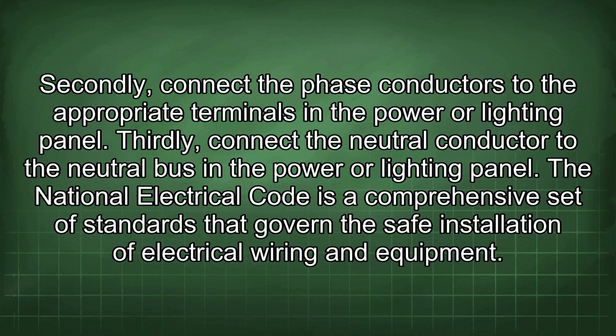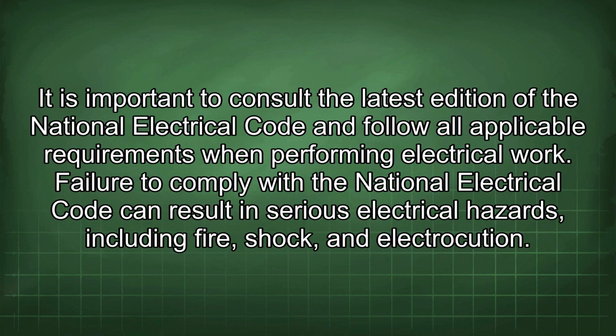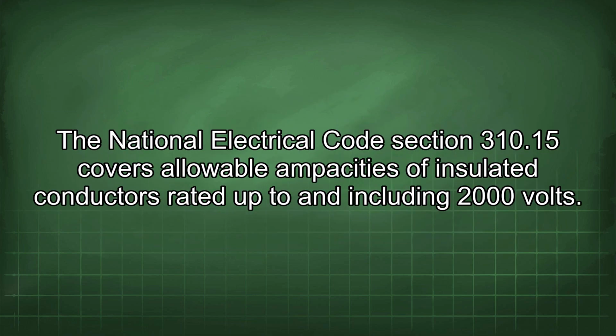The National Electrical Code is a comprehensive set of standards that govern the safe installation of electrical wiring and equipment. It is important to consult the latest edition of the National Electrical Code and follow all applicable requirements when performing electrical work. Failure to comply with the National Electrical Code can result in serious electrical hazards, including fire, shock, and electrocution. National Electrical Code Section 310.15 covers allowable ampacities of insulated conductors rated up to and including 2000 volts.